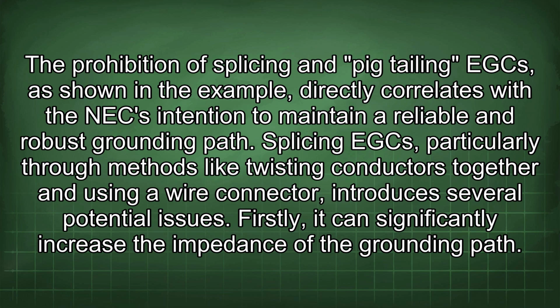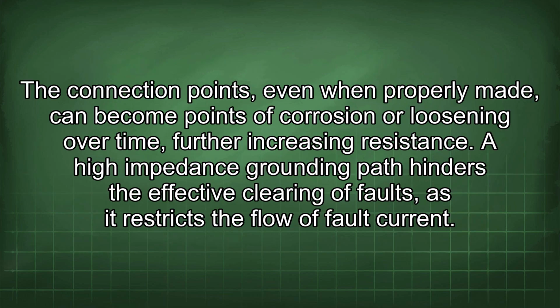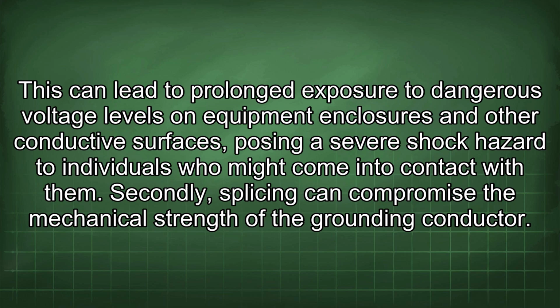Splicing EGC, particularly through methods like twisting conductors together and using a wire connector, introduces several potential issues. Firstly, it can significantly increase the impedance of the grounding path. The connection points, even when properly made, can become points of corrosion or loosening over time, further increasing resistance. A high-impedance grounding path hinders the effective clearing of faults, as it restricts the flow of fault current. This can lead to prolonged exposure to dangerous voltage levels on equipment enclosures and other conductive surfaces, posing a severe shock hazard to individuals who might come into contact with them.